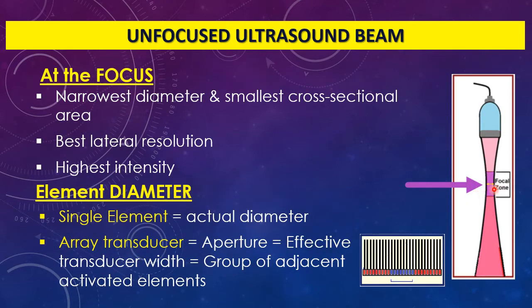At the focus, the beam has the narrowest diameter and the smallest cross-sectional area. This represents the best lateral resolution, since lateral resolution is related to beam diameter. At this point we also get the highest intensity, because intensity equals power divided by area — and since the cross-sectional area is at its minimum at the focal point, the intensity is at its maximum there.